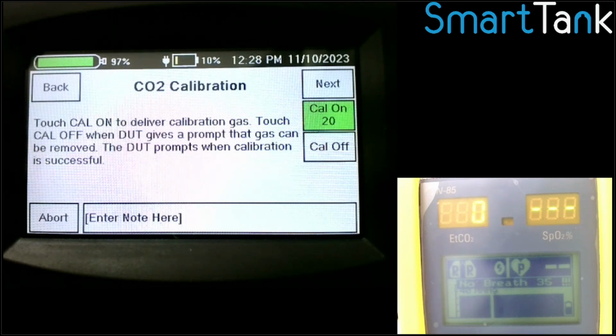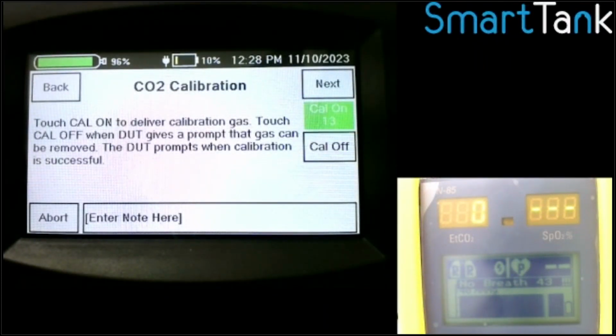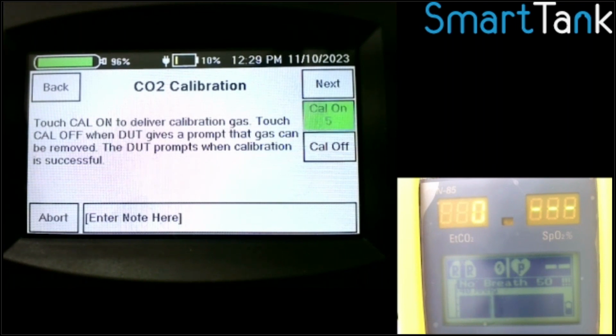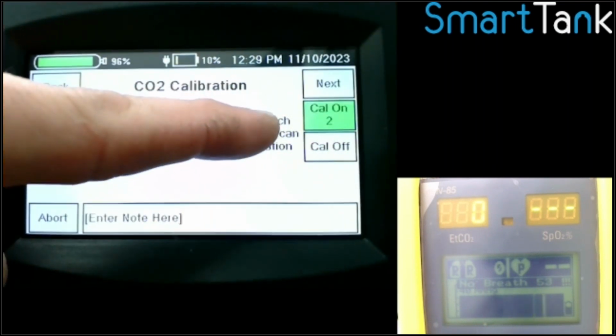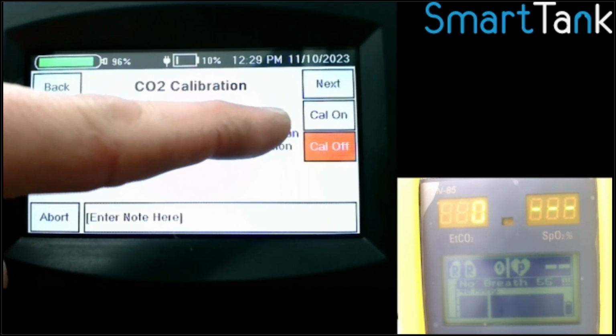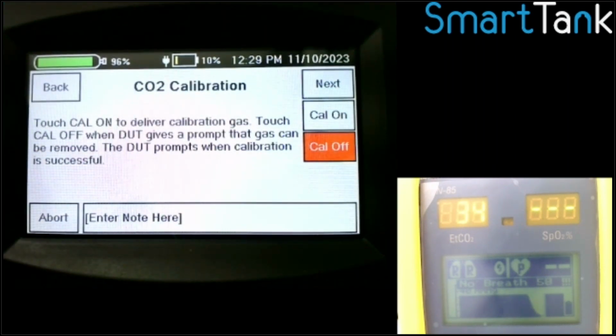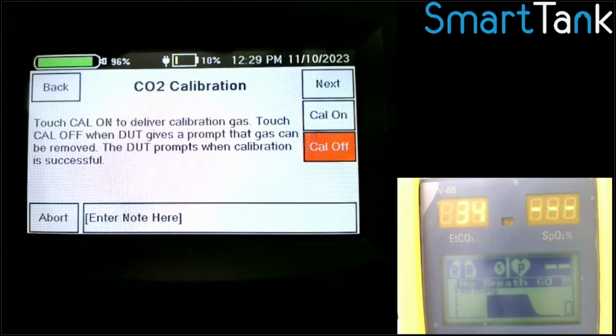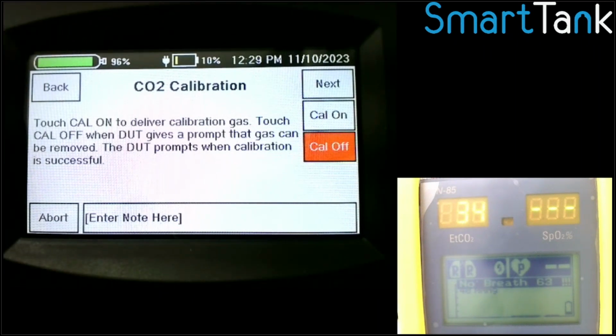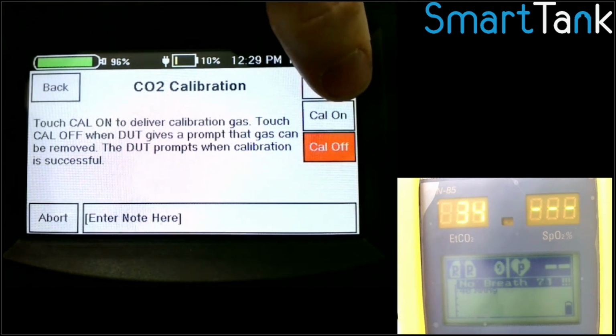Most of you probably use a regulator, and we've tested it. We've had customers test it. When you crack a regulator just a little bit, you're using 200, 250 milliliters minimum of gas. And so in this case, that would be 4 to 5 times more gas than you actually need for this device. The other thing we did that you'll notice right here is it's counting down. It will auto turn off. So if you happen to walk away, you don't burn through your entire gas bottle. You can always touch it and extend it, or adjust the timeout time to something else, or even turn that feature off completely.